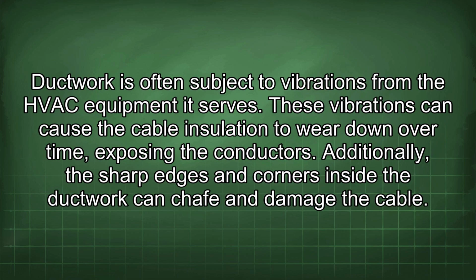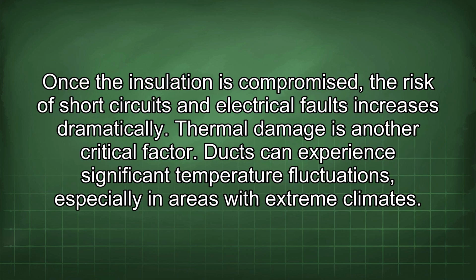Ductwork is often subject to vibrations from the HVAC equipment it serves. These vibrations can cause the cable insulation to wear down over time, exposing the conductors. Additionally, the sharp edges and corners inside the ductwork can chafe and damage the cable. Once the insulation is compromised, the risk of short circuits and electrical faults increases dramatically.